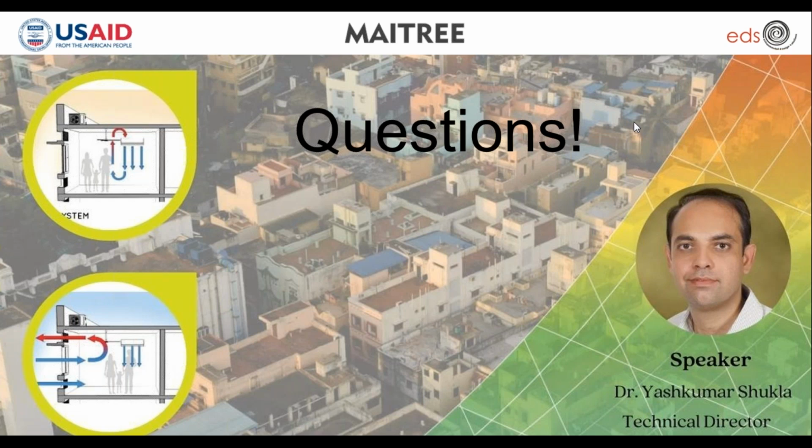Now, I am generalizing a lot just to simplify the message in the presentation. But the point is, as a designer, you can think about having a backup, or you can over design the system just in case the load increases. There are many factors that play into designing air conditioning systems and their sizes. But I think a fair bit of data now exists to be able to use alternate cooling systems, and not design for 22 degrees and the worst case scenario.